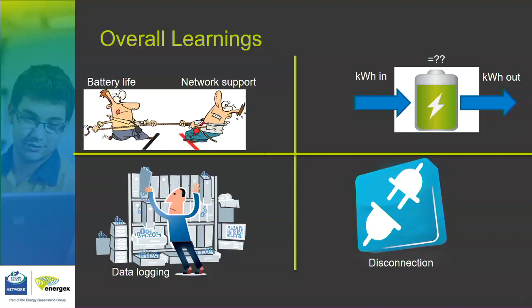Disconnection. We've noticed with a couple of our systems, when there's a fault, it basically runs for the hills, trips itself off, not caring how much export or import it's doing. That's a real problem because we send step voltages up and down our networks when these trip off by accident. What we're finding is we need a much nicer situation where they start to ramp themselves down if there's a fault, so that when they do disconnect, you don't see a bump on the network. That takes a bit of integration work between the batteries, the inverter, and the overall control system, but it's much, much nicer to our network overall.